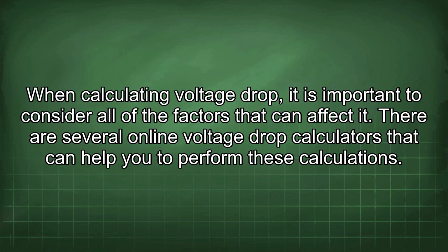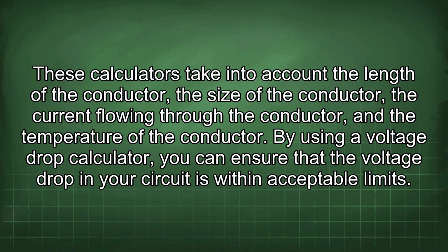When calculating voltage drop, it is important to consider all of the factors that can affect it. There are several online voltage drop calculators that can help you to perform these calculations. These calculators take into account the length of the conductor, the size of the conductor, the current flowing through the conductor, and the temperature of the conductor. By using a voltage drop calculator, you can ensure that the voltage drop in your circuit is within acceptable limits.